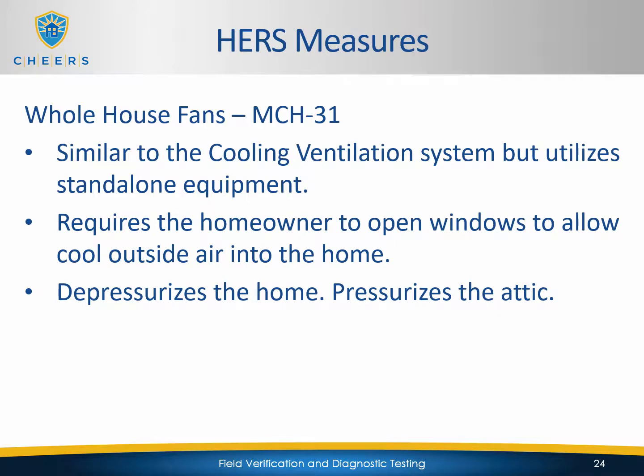Whole house fans are going to be the MCH-31, and these are very similar to the cooling ventilation system, but they use standalone equipment. This does require the homeowner to open windows to allow cool outside air into the home, and this one depressurizes the home and pressurizes the attic. So we saw that the cooling ventilation system pressurizes the inside of the home, and the air is pushed out through windows or relief ducts. This is exactly the opposite. This fan is installed in the ceiling itself, and it's going to push air up into the attic.